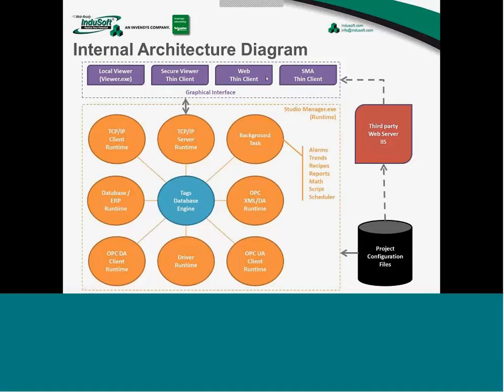Regardless of the type of graphical interface used to access the graphical screens, and by the way, they are not mutually exclusive. You could have all of them happening at the same time on the different browsers on different stations. They all communicate with Studio Manager through the TCP/IP server. And everything that we're going to see here and talk about is the graphical interface, so everything will be executed by those modules in purple. The local viewer, the secure viewer thin client, the web thin client, or the SMA thin client. And those graphical interfaces will exchange tag values with Studio Manager via TCP/IP.